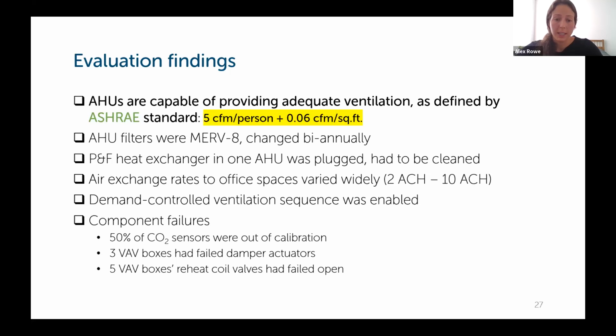The engineer also noted that the air handling unit filters were MERV 8 and changed biannually. The HVAC contractor found that a plate and frame heat exchanger in one of the air handling units was plugged and had to be cleaned, which had to be done in order for the testing and balancing contractor to do their work. So that not only restricts airflow, but it reduces heat transfer from the exhaust stream to the outside air stream, and also ends up using more energy because you have to use more heat from the boiler plant. So it's great that they noted that and fixed that.